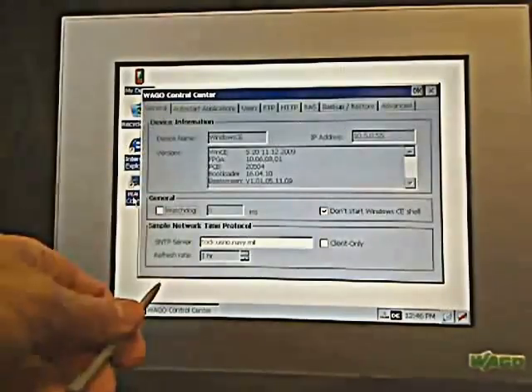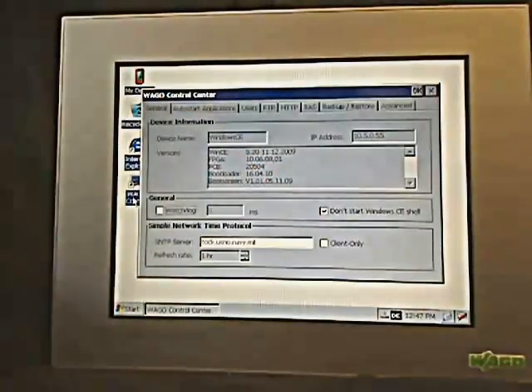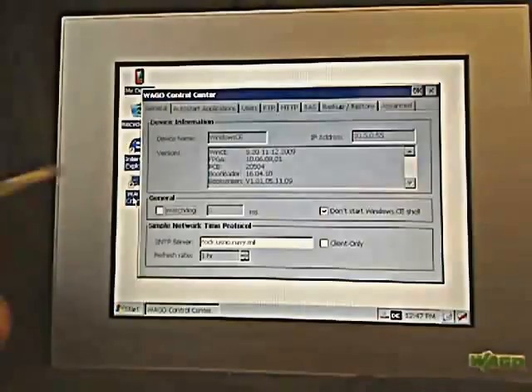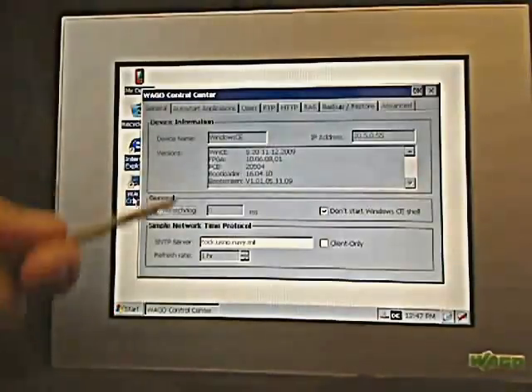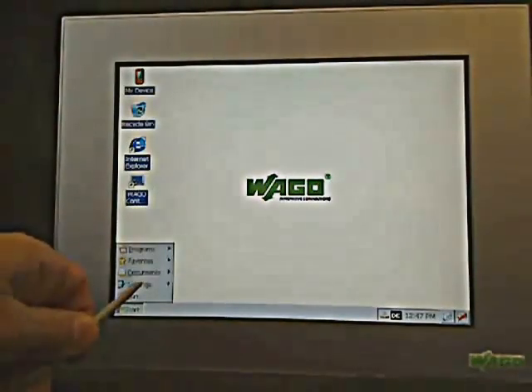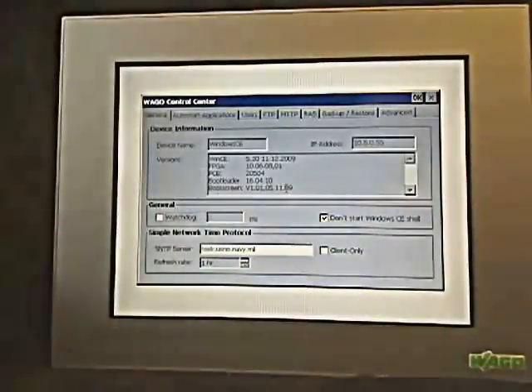One of the other things I can do is come into the control center and select 'don't start Windows CE shell.' When I do a reset of this device and it starts up, it's going to go into the actual executable code or allow me to access the device and load the code onto the panel itself. I can select that, click OK, it saves to the registry and flash, and then I can do a soft reset. Now I can access the device and run a program on here and load that program.